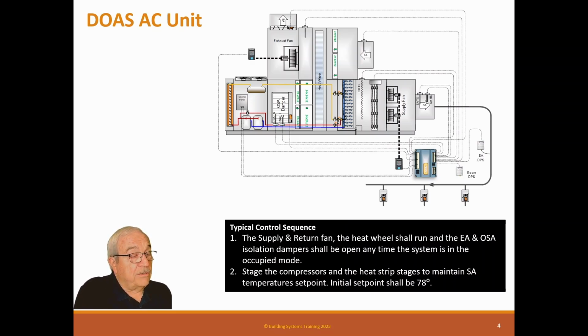Since these are makeup for other package units, the intention is to trim off the outside air, so we're supplying basically return air conditions to the unit. So the unit doesn't see this outside air load. It's only seeing the building load, which gives them a little bit better and allows us to do all that complicated stuff all in one unit. So if we want dehumidification mode, we can dehumidify this air right here. So these other units that are getting the air don't have to do that. We'll do it all here.